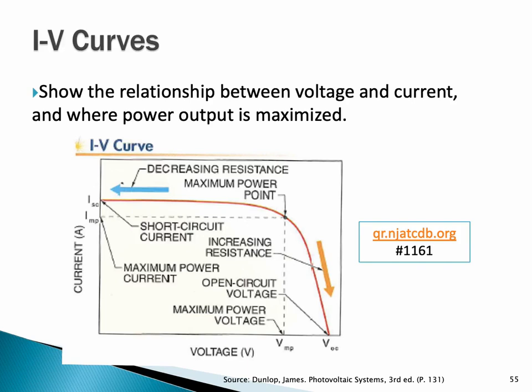Once I engage that module or array, make it do work, then I have IMP, or current at max power, and that would be at 1,000 watts per meter squared. On the horizontal axis, 0 being on the left, maximum volts on the right, VOC, volts open circuit. That is when I have no connection to the module or array, and I read a voltage. That's maximum voltage, no current flow.